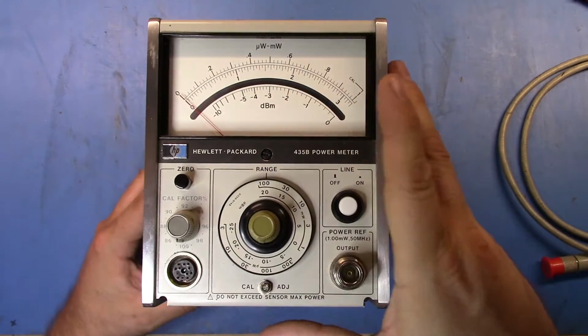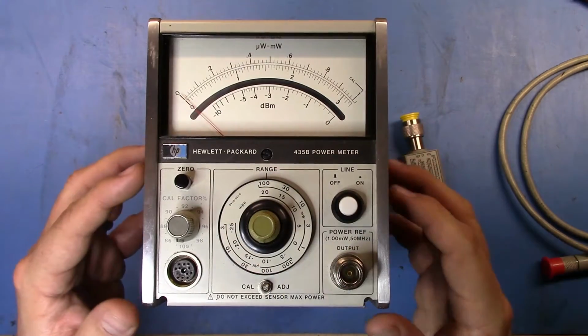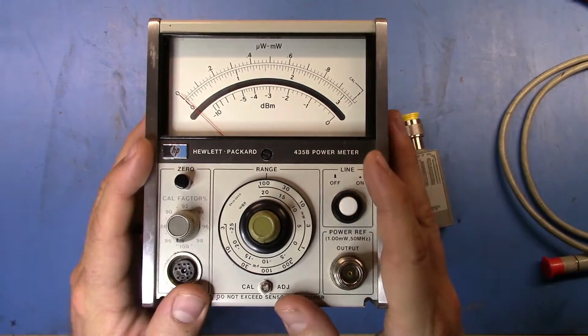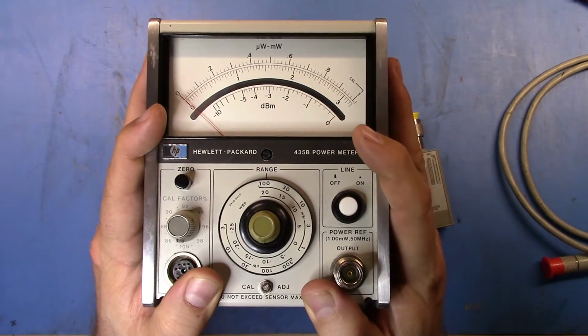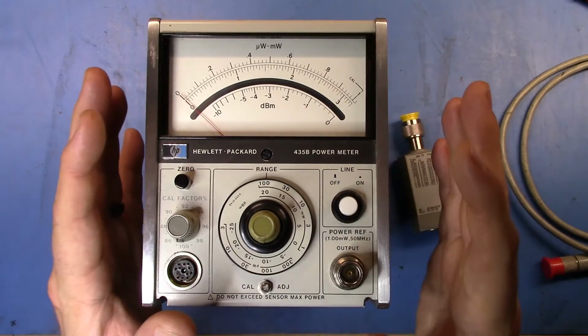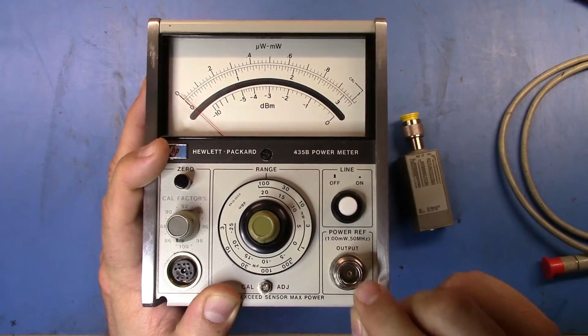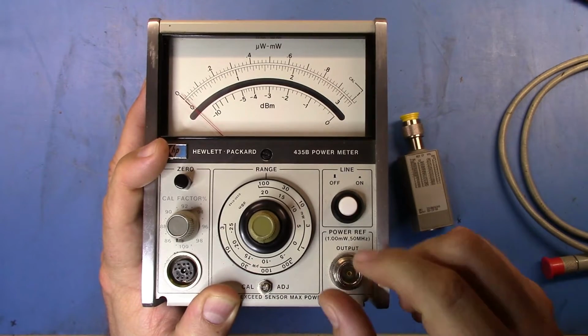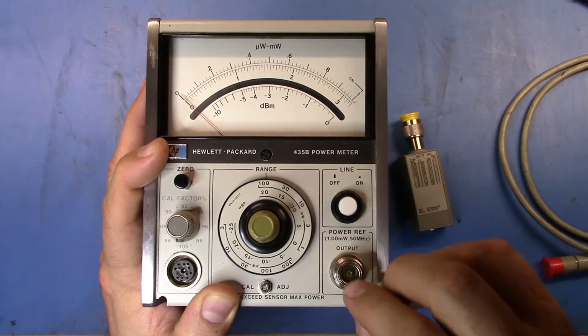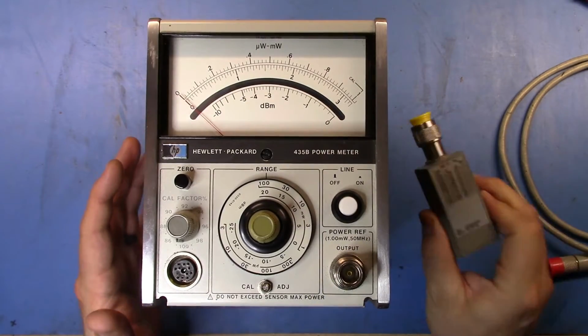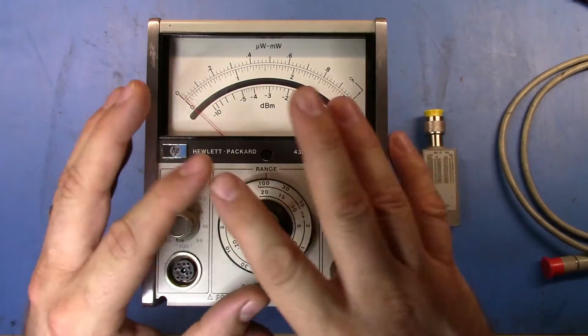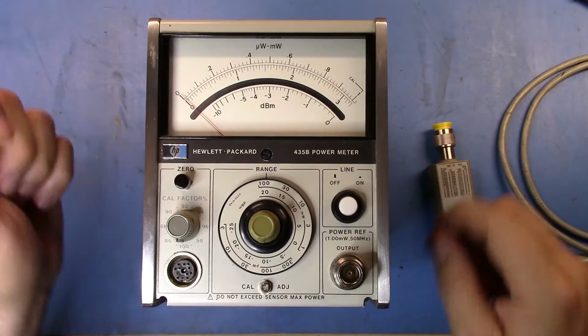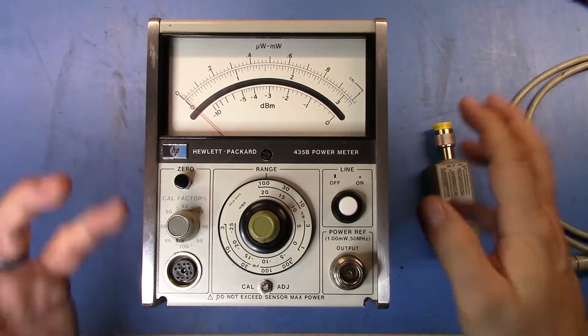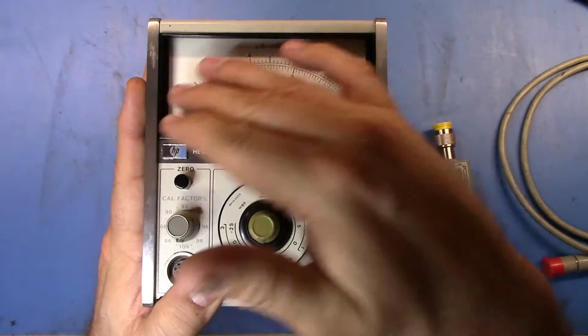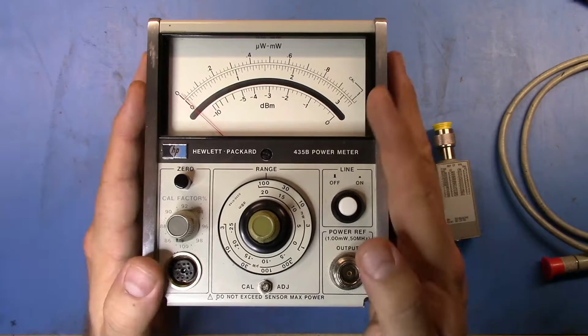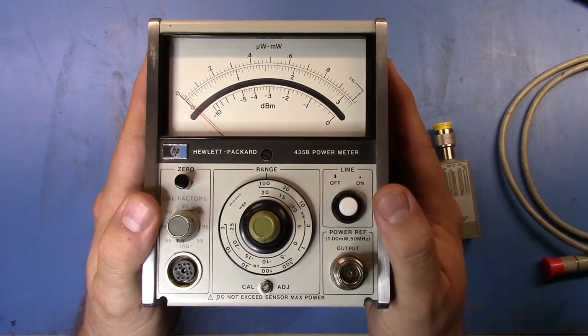This then tells the underlying mechanics what power range we're going to be in when we're reading, so that the meter can give an accurate reading. And then because all of these things are basically reference measures, you need to have a power reference, and these are very accurate 50 megahertz, 0 dBm, or 1 milliwatt power reference. And so I can attach this to the power reference here and set that reference point. Now I know what 1 milliwatt is, so now I can go read microwatts or watts or so on, depending upon the sensor that I have. So that's the basic operation. You can see it here. What I'm going to go do now is just take the covers off and let's take a look inside.